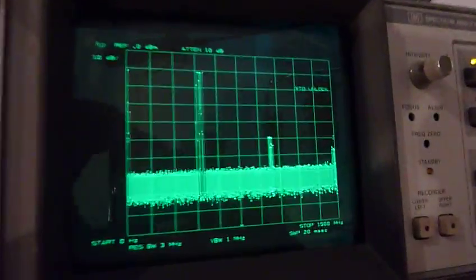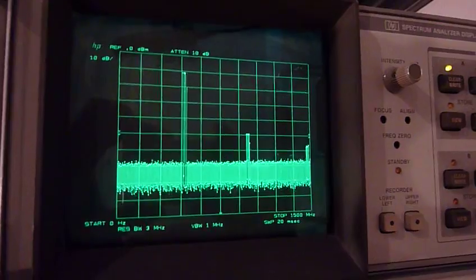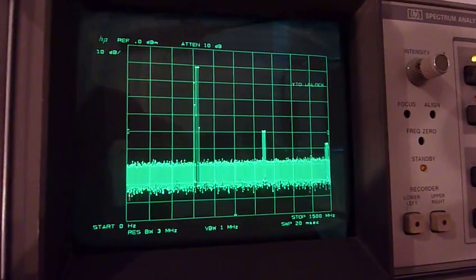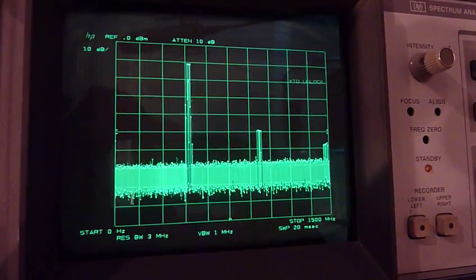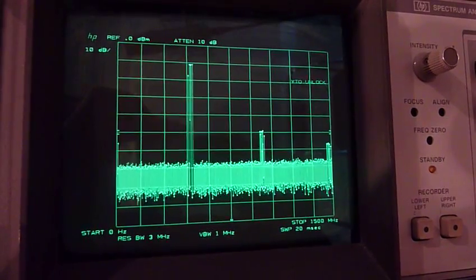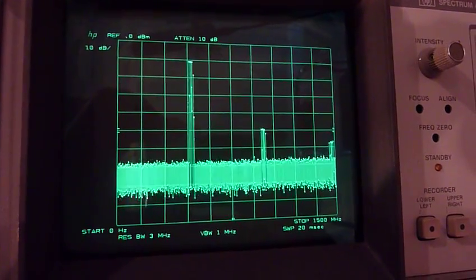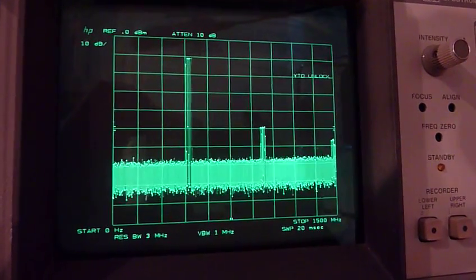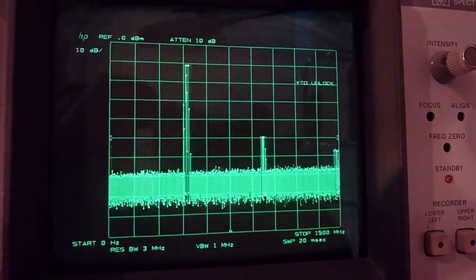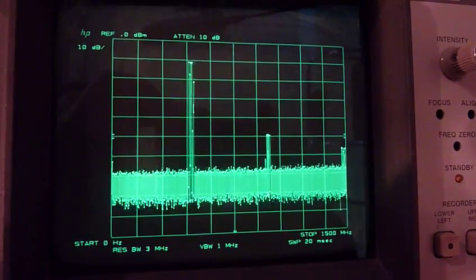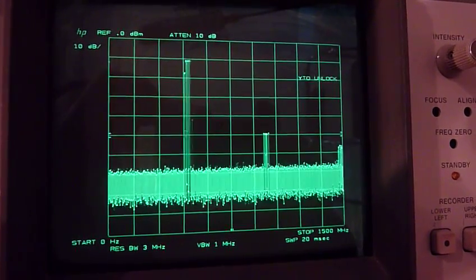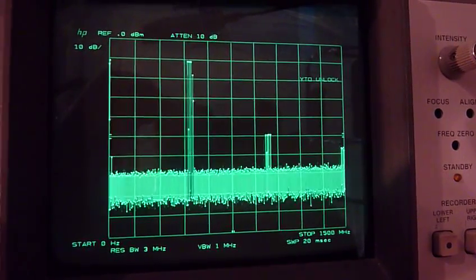I downloaded the repair manual and I was reading up on it and I understand that there are actually three ways that the YTO is tuned depending on the frequency span. And this is the biggest span at 1.5 gigahertz of span. And you can see the YTO unlock fault.